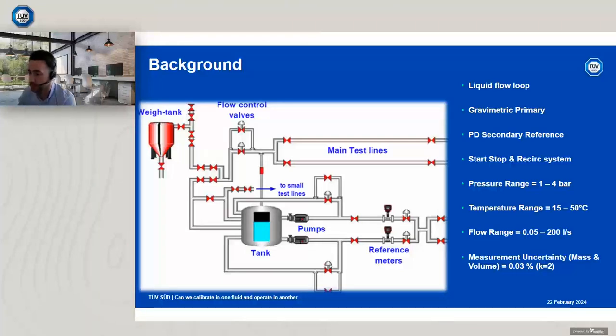It has a gravimetric primary reference system, so a weigh tank, and it has PD secondary reference meters. It can operate in stop-start mode against the weigh tank or in recirculation mode via the PD meters. Pressure is relatively low, in the region of about 1 to 4 bar, and temperature range going from nominally 15 to 50 degrees Celsius, with a flow range of 0.05 to 200 litres a second.